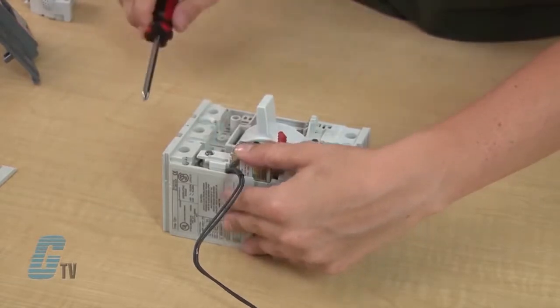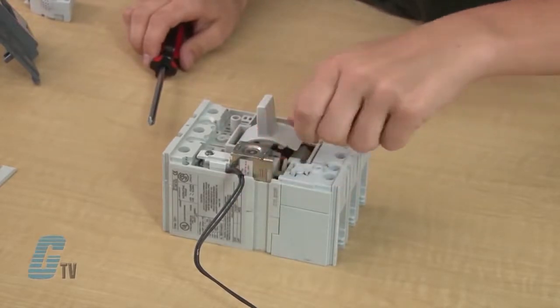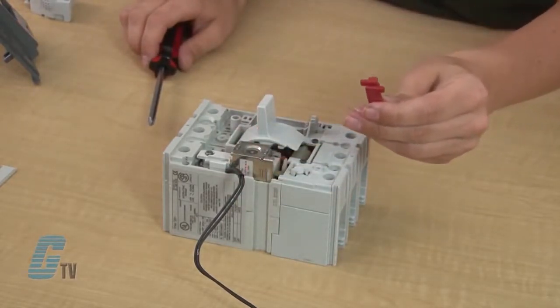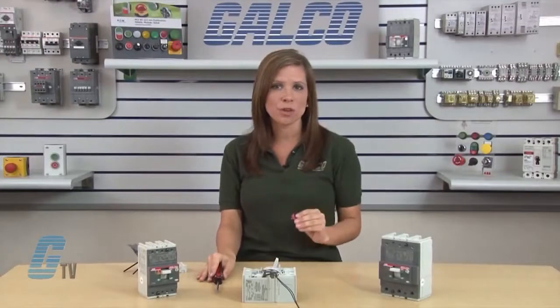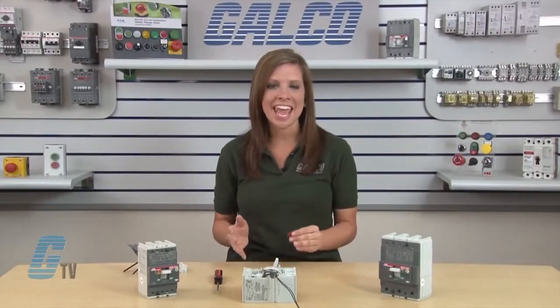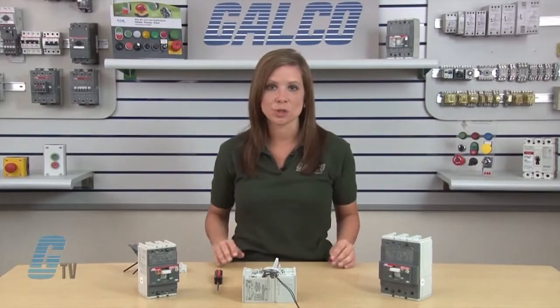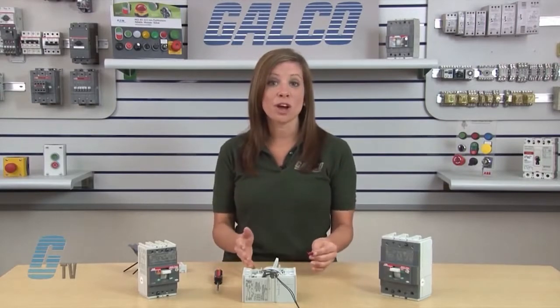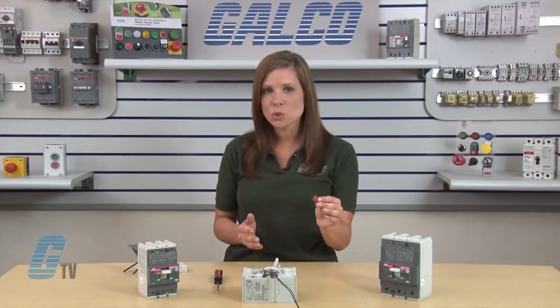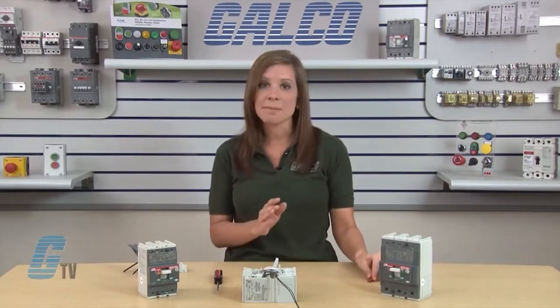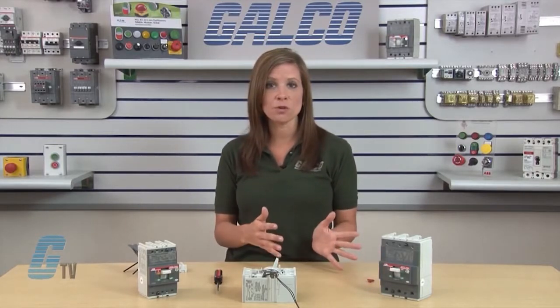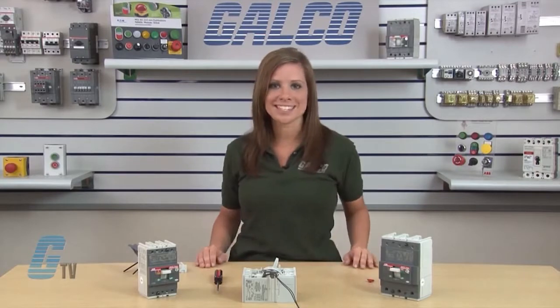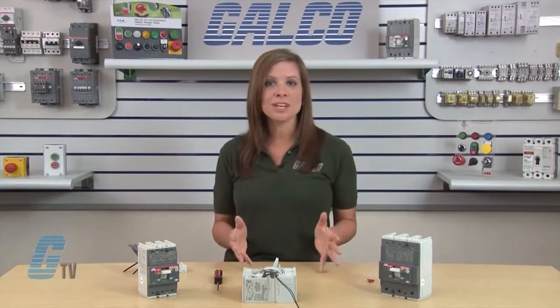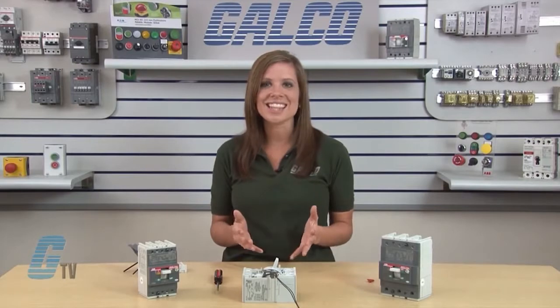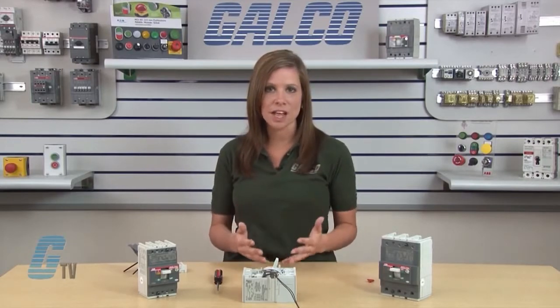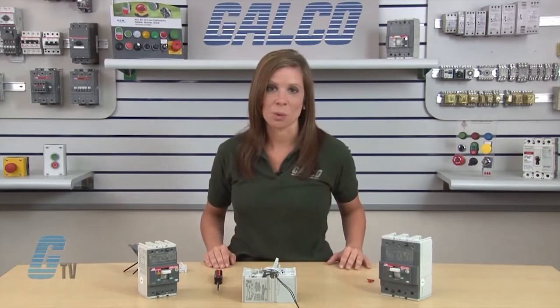When holding the UVR unit in place, the installation tool may become loose and fall out. This is acceptable providing that the UVR unit is being held in place by hand until it is fastened to the circuit breaker's frame. Once the UVR is installed, the installation tool will no longer be needed. It may be kept for future servicing of the UVR and breaker, or it may be set aside for recycling. The trip unit is properly installed when I can see that the back of the trip unit is mounted flush with the back of the accessory port.